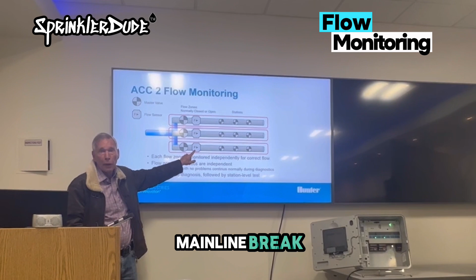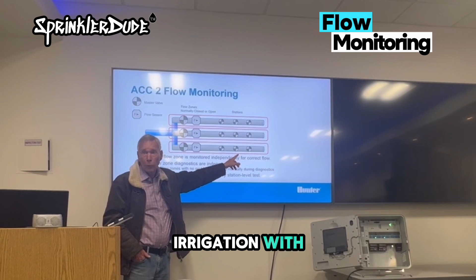But if the flow does drop, we know the problem is downstream, in the valve or combination of valves that's running. So it samples each valve that was running at the time the alarm occurred, to see if it's working to spec or not. The ones with high flow, it kills, and then resumes irrigation with the ones that pass the test. You'll get alarm messages in the logs and to your phone about the stations that are broken.